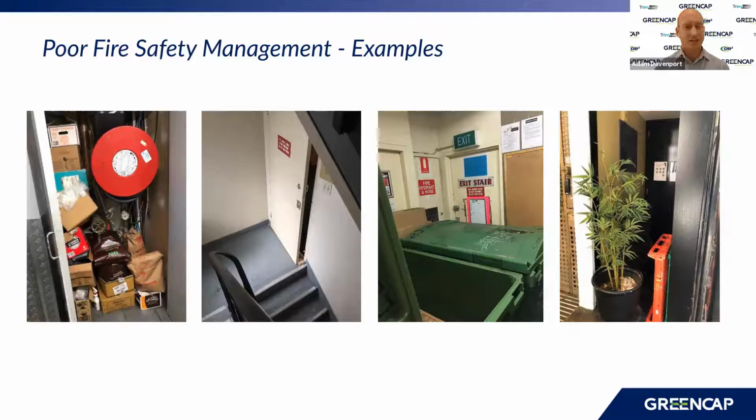So let's try and have a look when we're trying to prepare our buildings for emergencies, that we keep all of our items out of these cupboards. Cleaning materials are the worst that we normally see. Then the second photo is the fire door. Now this is chocked open, and there's a definite problem when it comes to a fire being in, say, that floor and breaking compartmentalization. So those doors lead into a fire restricted environment.